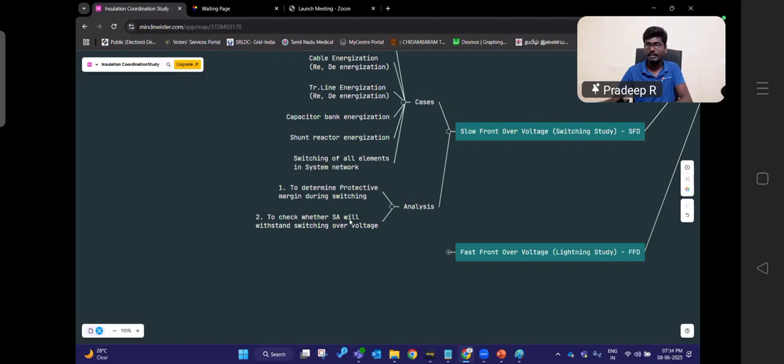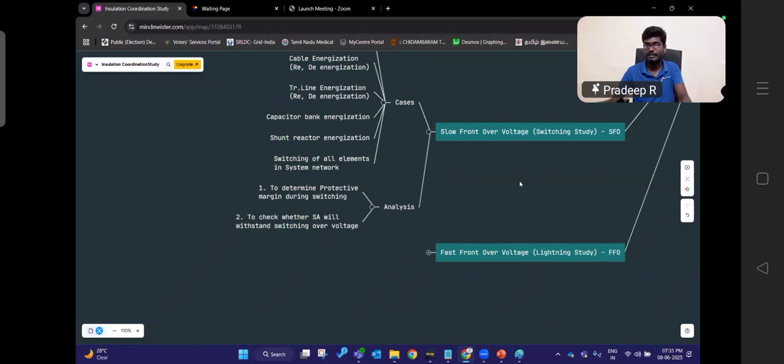When it is like 1.21 or 1.22, it is marginally protective. When it is like 1.9 or 2, it is overprotection. For example, 1.2 is the bare minimum; it should be within 1.35 to 1.4. That is enough for our system, which will be cost effective, with everything within range.